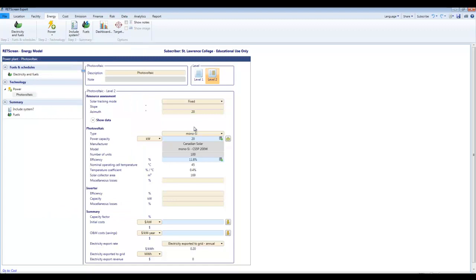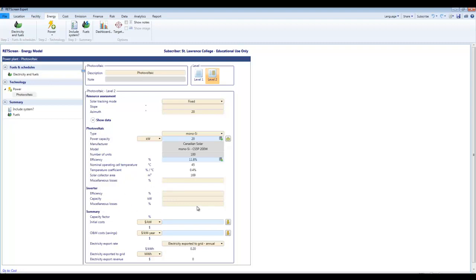Hit the check mark and it pastes that data into here. So moving forward I have to specify losses. Both there's two places put losses. Miscellaneous losses and losses under inverter. I'm going to put four percent miscellaneous and zero for the inverter. Here's where the efficiency of the inverter goes. I'll put 97. Here's where the capacity of the inverter goes. Well it better be 20 kilowatts or better. That goes there.